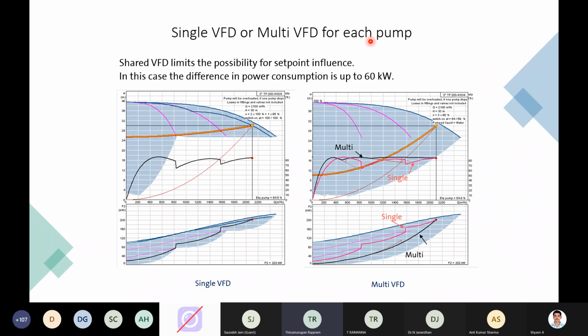The multi VFD situation is like this: you have three pumps. Instead of having one VFD common for all three pumps, we can move to one individual VFD for each pump. So there will be some increase in your capex, but the impact on your energy saving is very, very immense. And whatever you have invested in excess, you can recover within a 2 year time period. So one thing is this is the single VFD concept. When you compare it with multi VFD, obviously you can find the energy difference in these two cases. It is much higher for a single VFD and very low for multi VFD.